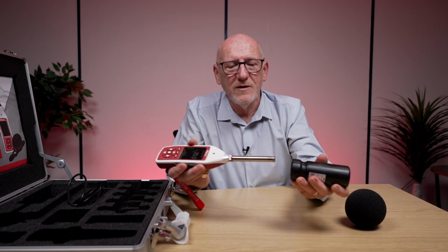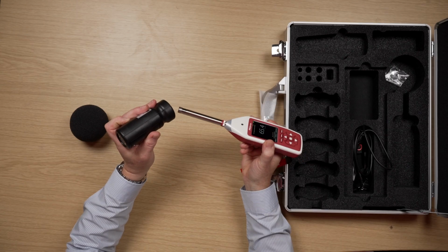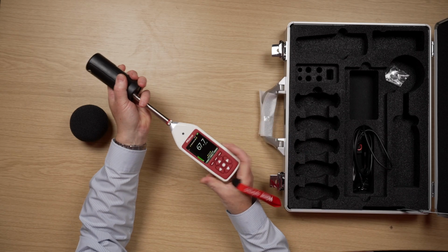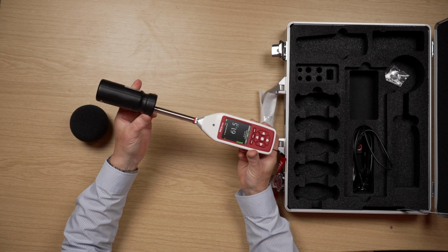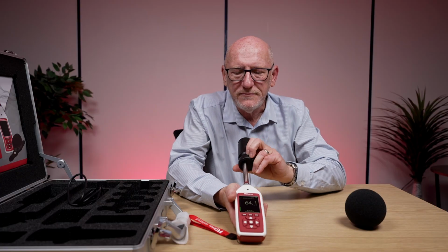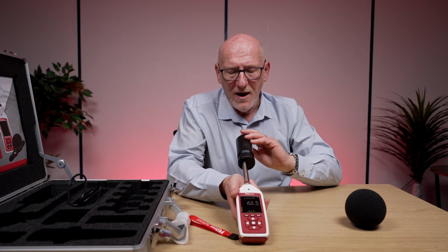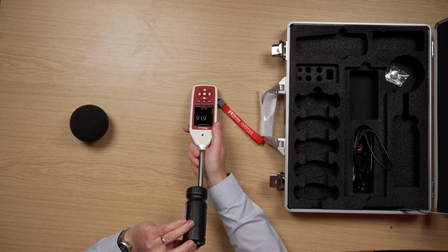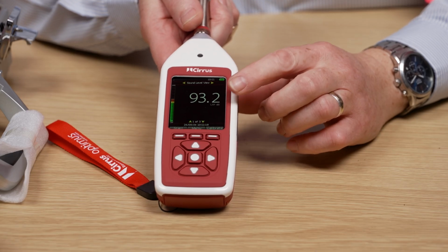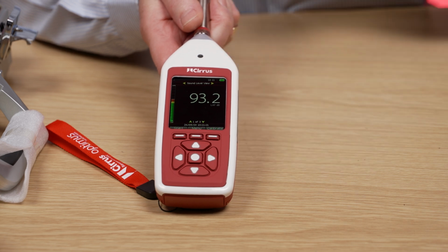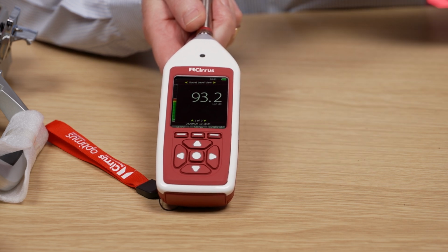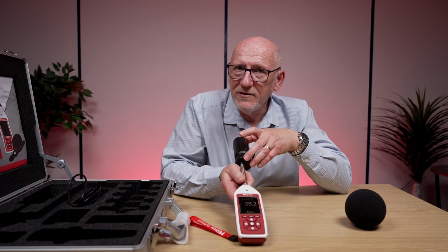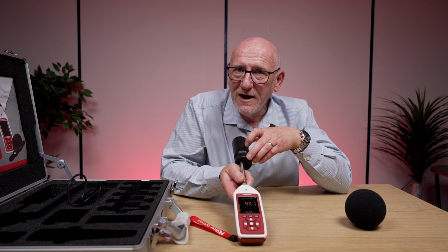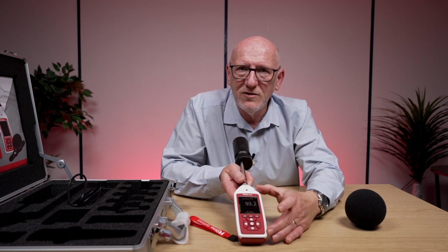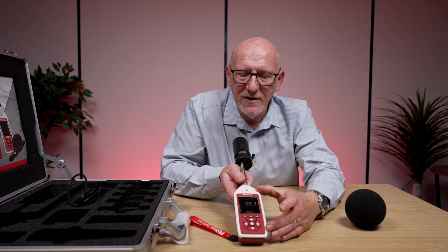So I'll do it this way around so you can maybe see it. So it's going to go into this hole, and I'm just going to push. It doesn't go in very far. So now I've got the calibrator on, and what I'm going to do then is turn this on by pressing the button. And what you'll see when you look at the screen is you'll see a constant noise level. That's because your calibrator is generating a tone, usually 94 decibels or thereabout, at 1 kilohertz. And we're going to use this tone in the sound level meter to calibrate the instrument.